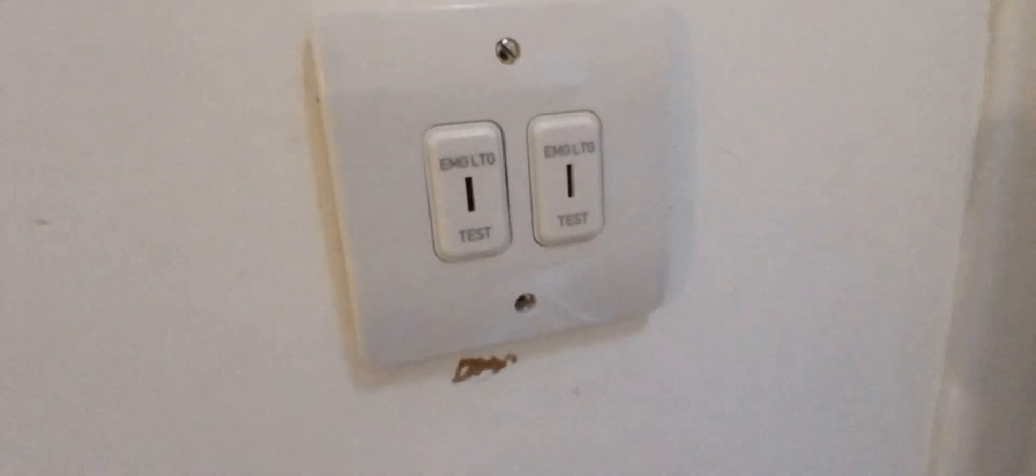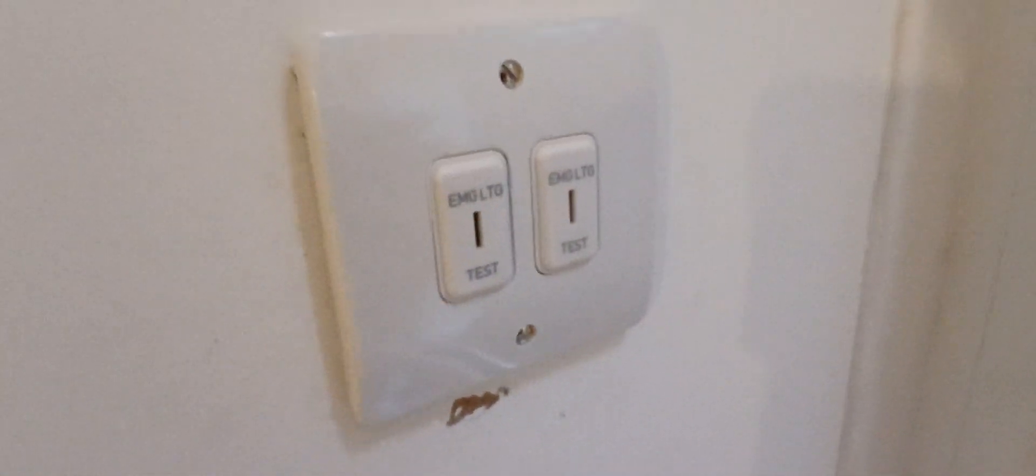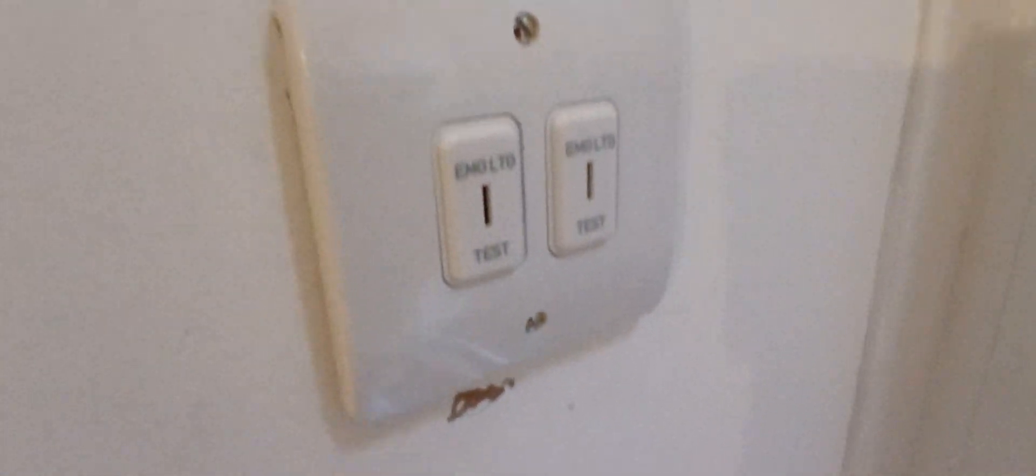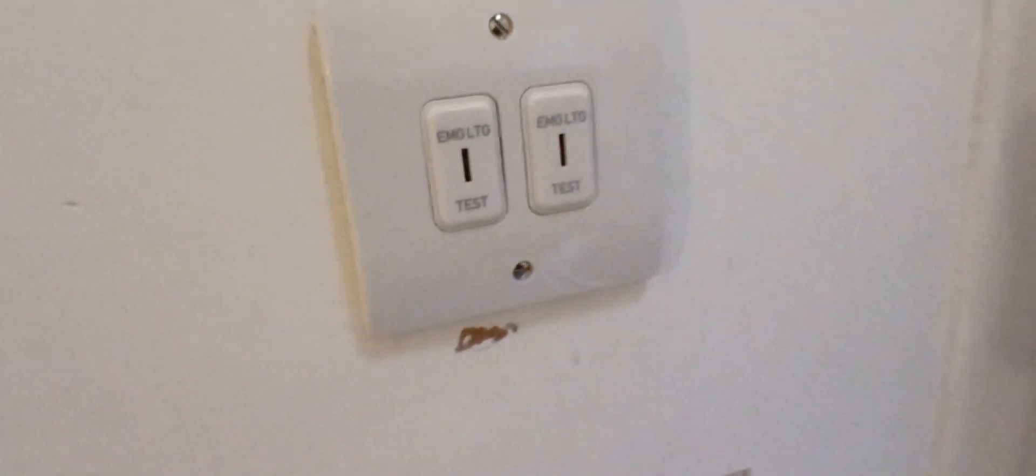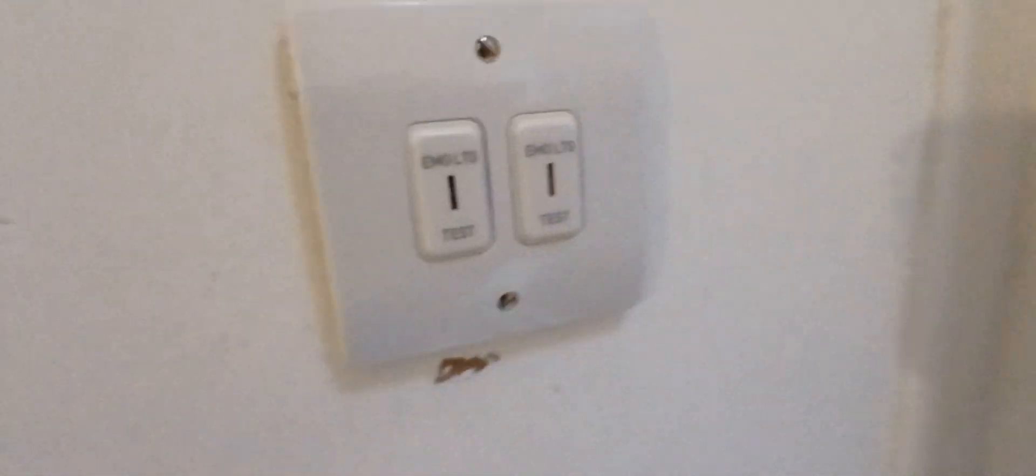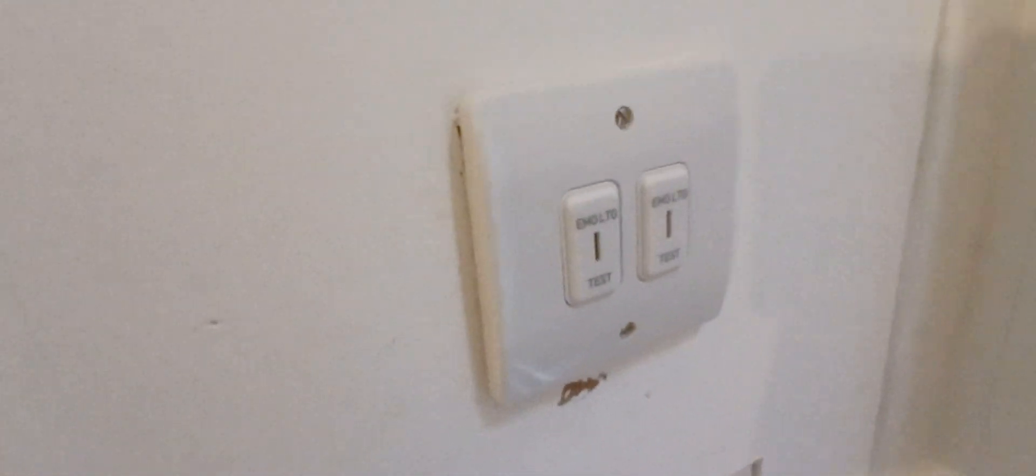A lot of people have been asking how to use these fish keys from the key switches to test the emergency lights.